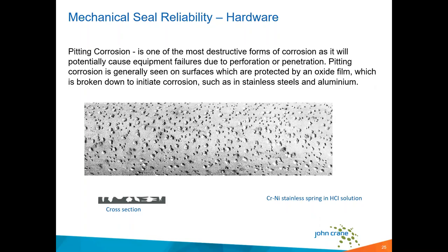So concentrated corrosion, for example, in a metal bellows seal where you have relatively thin cross-section metal plates, this type of corrosion can basically rapidly perforate through those thin wall sections. So we have to look at the metallurgy, the material of the bellows at that point, and determine if that's really a cause of failure.